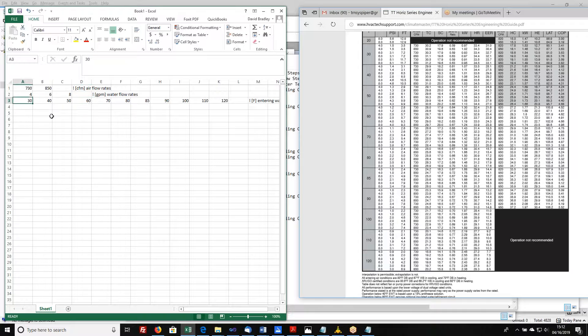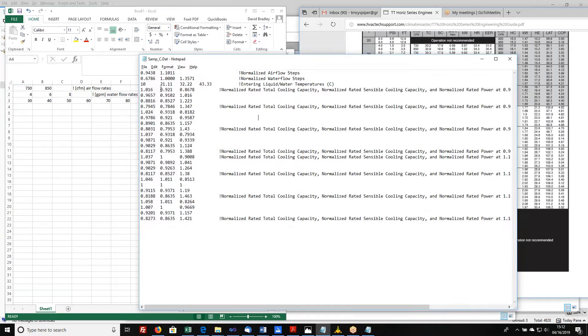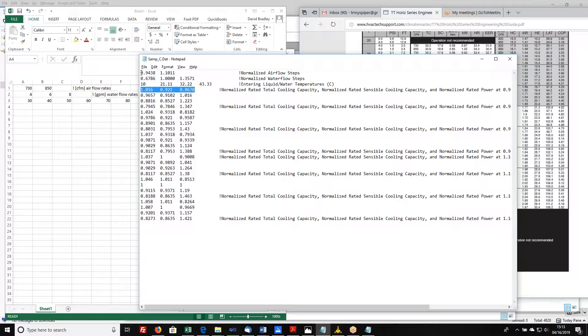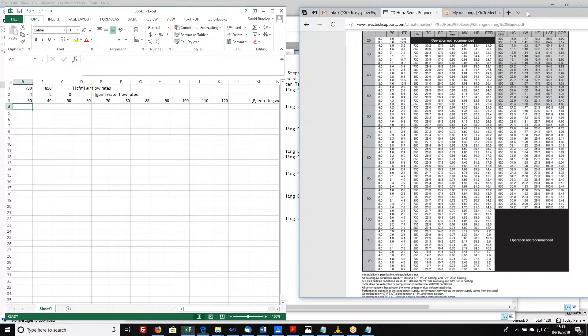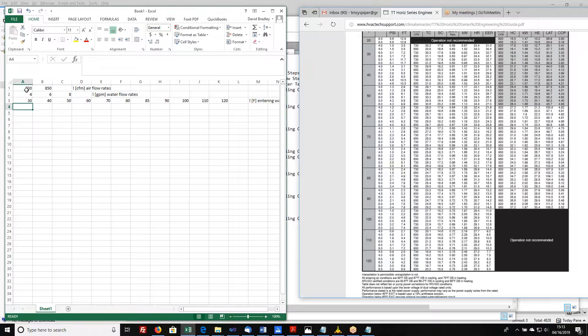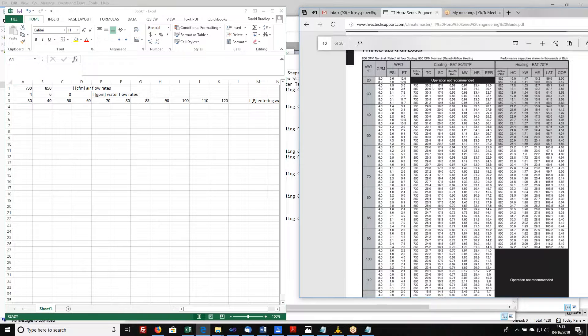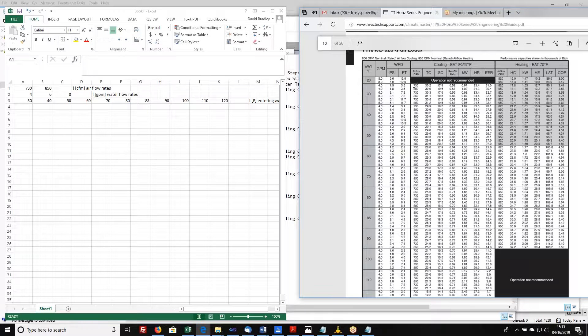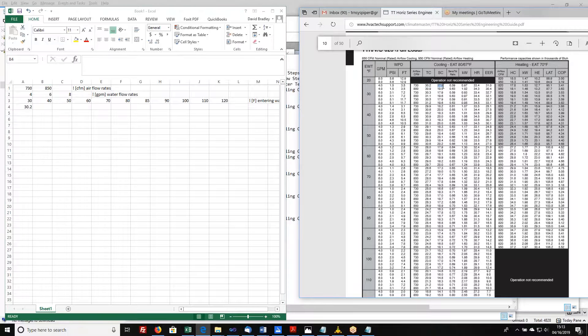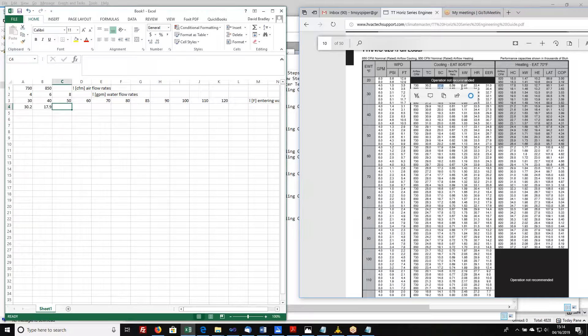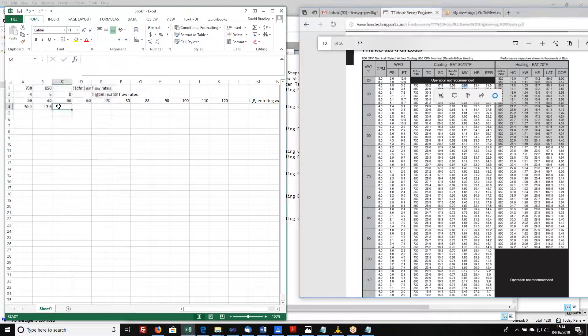Now on to the dependent variables. Referring back to the sample data file, I need 3 values for each combination of these points. So this first data point here is going to correspond to this first air flow rate, the first water flow rate, and the first entering liquid temperature. So let's go over here and look at what we've got. At a value of 730 CFM, 4 GPM and 30 degrees Fahrenheit entering water temperature, what I need to know is the total cooling capacity. Total cooling capacity is 30.2. Next I need to know the sensible cooling capacity. That says it's 17.9. And then I need to know the power consumption. So that is 0.97.